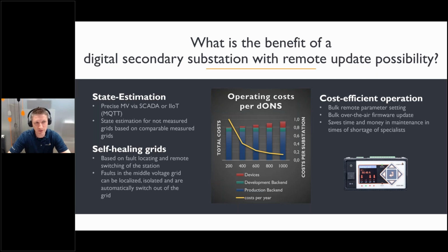Then big topic for the future, self-healing grids. If you have the goal in future of self-healing grids, you have to install at first the sensors and also the actors in your field. And this is done by such digital secondary substations. So not only remote indication, but also remote control. And if you have enough sensors and actors, enough digital secondary substations installed in a certain field of your grid, then it will be possible in future to detect faults in the middle voltage grid, automatically isolate them, and switch them out automatically. So to achieve this goal, you need to install first the sensors and actors.